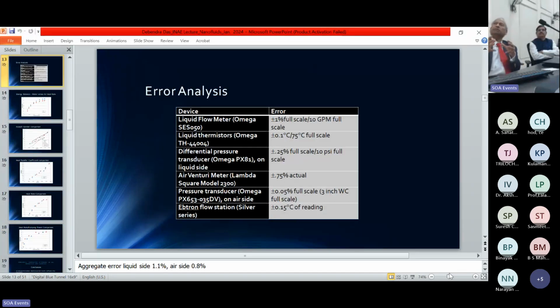Every instrument you use has inherent error because none of the instruments are perfect. So we have a liquid flow meter, Omega makes it, and Omega tells that this liquid flow meter has an error of plus or minus 1%. We have liquid thermistors which measure the temperature. Those thermistors have inherent error of plus or minus 0.1 degrees Celsius. We have a differential pressure transducer. It has an error of 0.25% full scale error in the pressure, because all these are very accurately measured by their manufacturer, and the manufacturers give us these numbers.